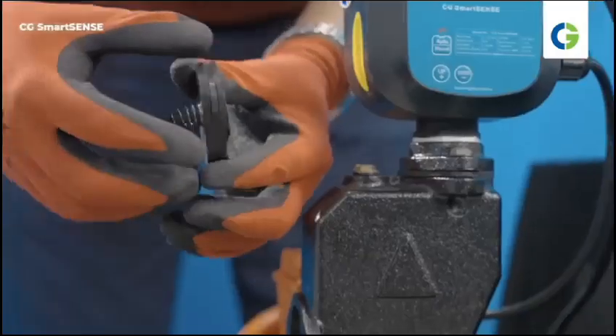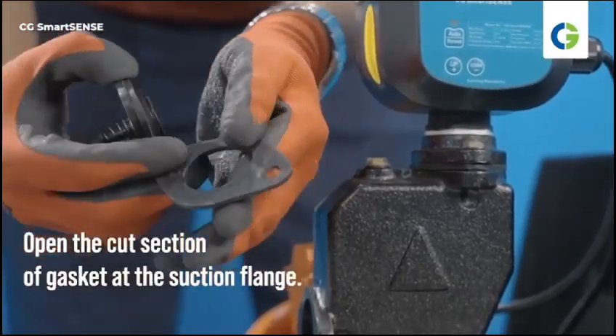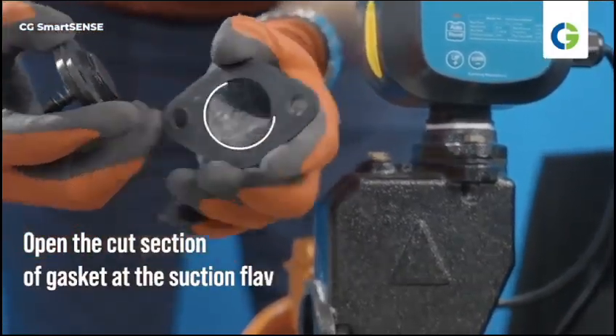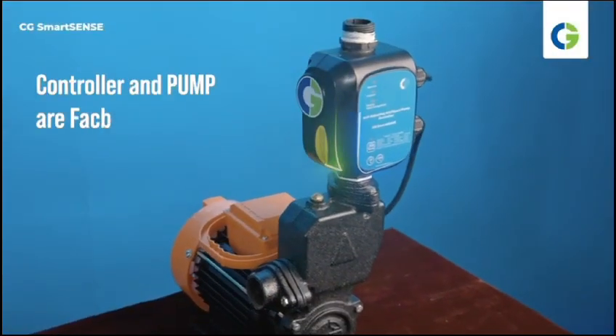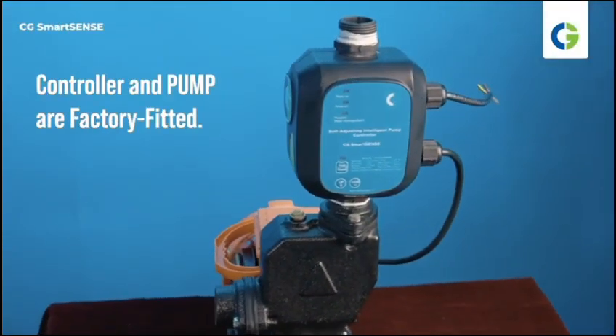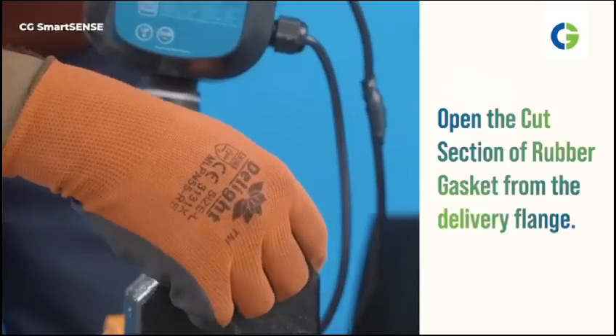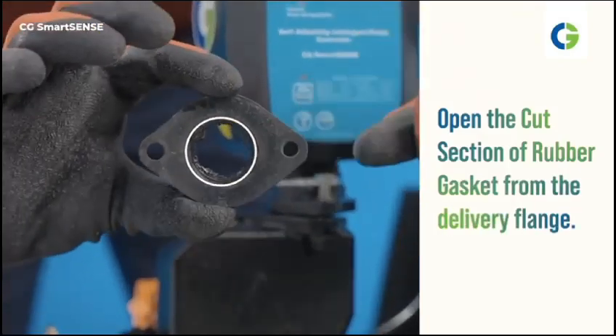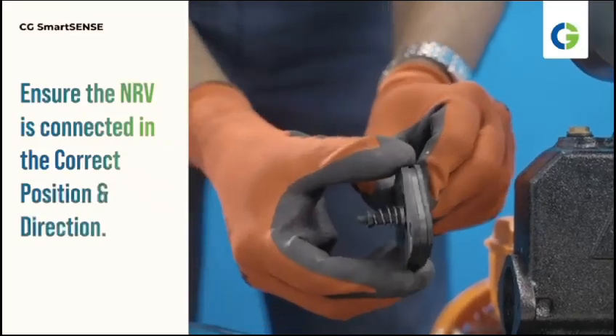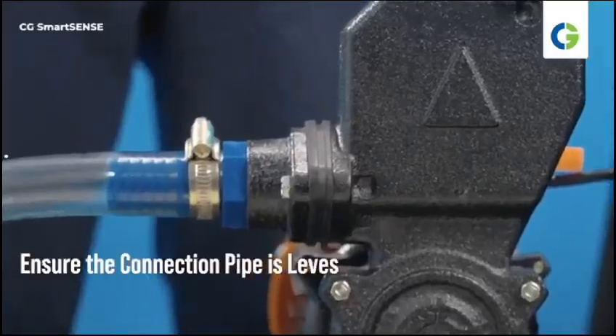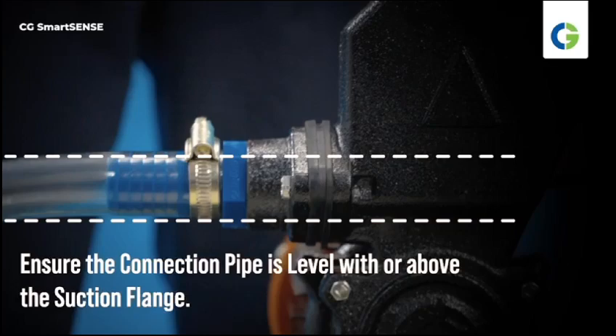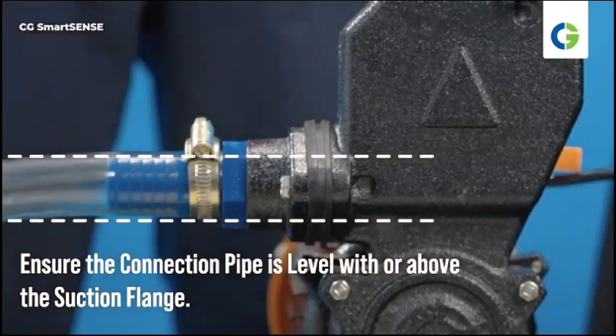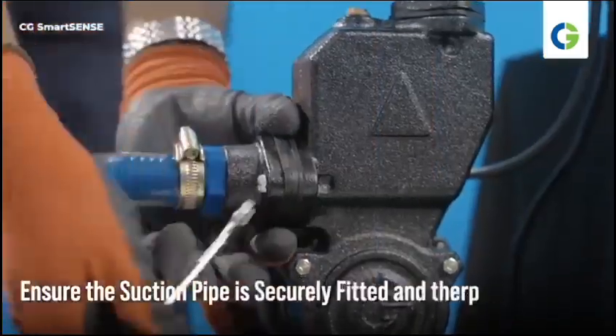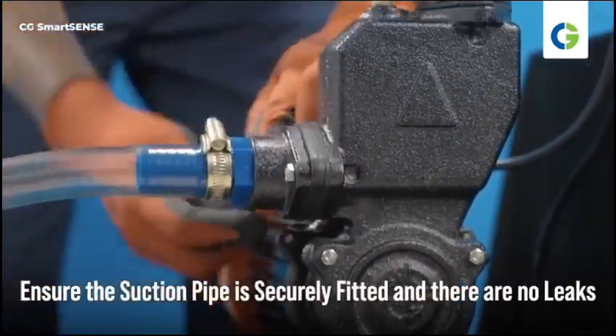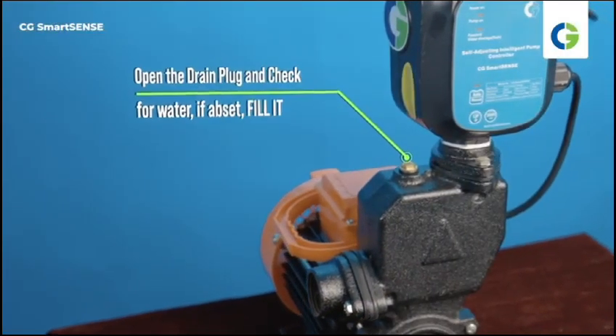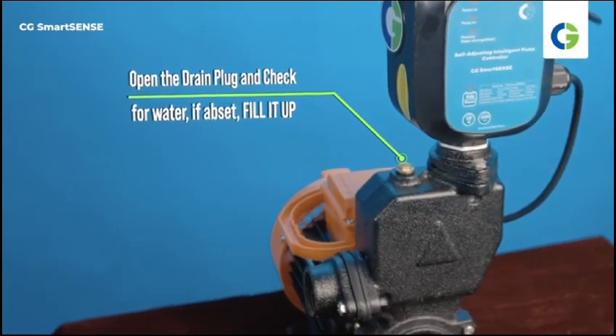You must remove the cut portion of the rubber gasket at the suction flange. The product comes factory fitted with a controller and pump. You must open the delivery flange and remove the cut portion of rubber for pump operation. Make sure the NRV is connected in the proper position and direction. Ensure the delivery line is at the same height or above the suction flange. This will help sense the water quickly. Ensure the suction pipe is fitted tightly and there is no leakage. Open the drain plug and check for water. If no water is found, then fill the water.